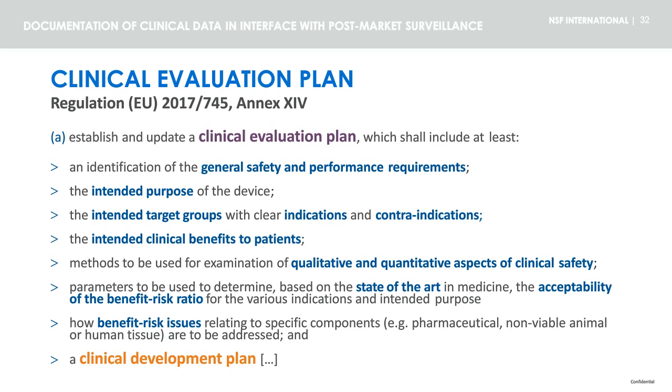a specification of methods to be used for examination of qualitative and quantitative aspects of clinical safety, a specification of parameters to be used to determine the acceptability of the benefit-risk ratio for indications and intended purpose of the device, and an indication of how benefit-risk issues relating to specific components will be addressed. And, importantly, it should also include a clinical development plan.